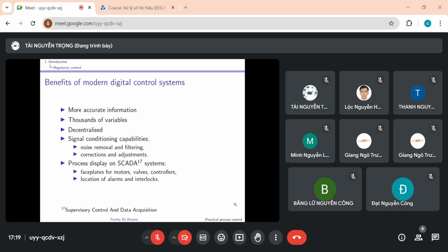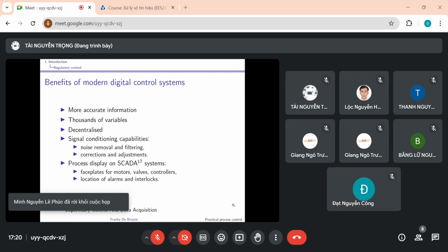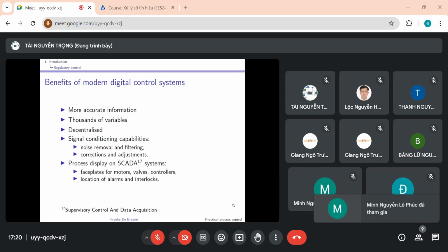These systems have signal conditioning capabilities, so for instance noise removal and filtering, but also calibration possibilities of the different measurements. You can easily interact with the system using the HMI or supervisory control and data acquisition system, SCADA system. In the case of Siemens, it is the Windows control system WinCC. You can interact with the system through faceplates for motors, valves, controllers, and the alarms pop up and they make it easy for you to locate the problem or the interlock.